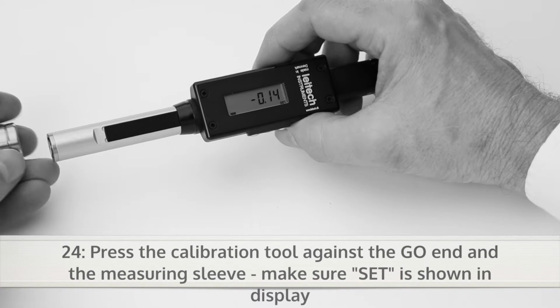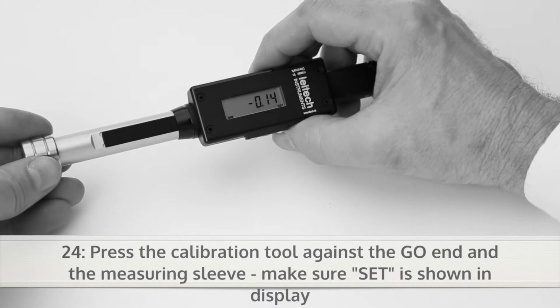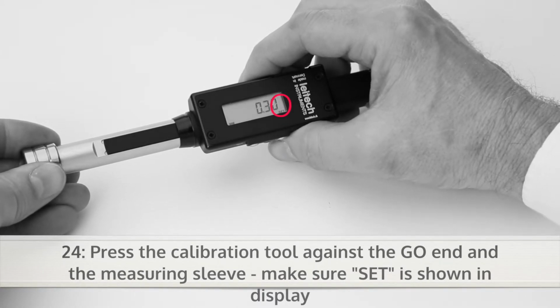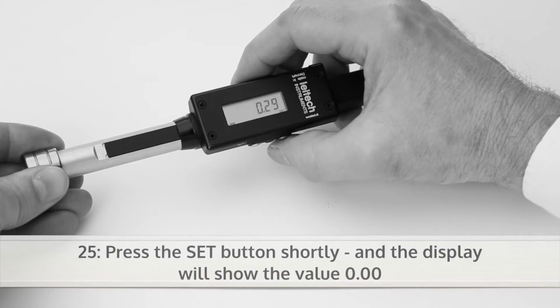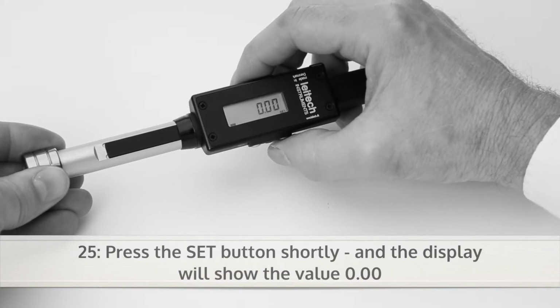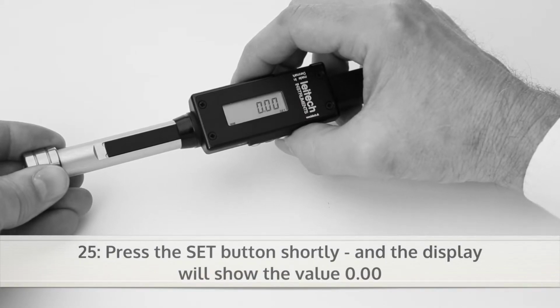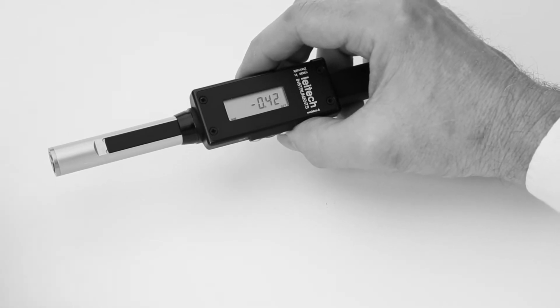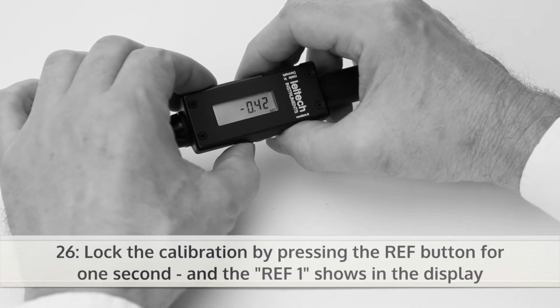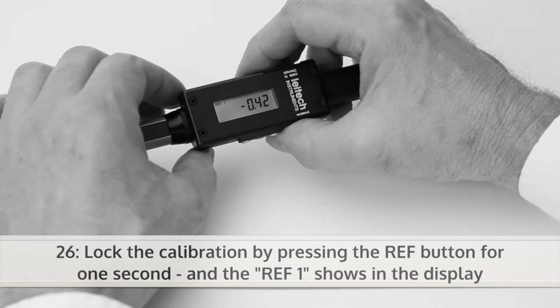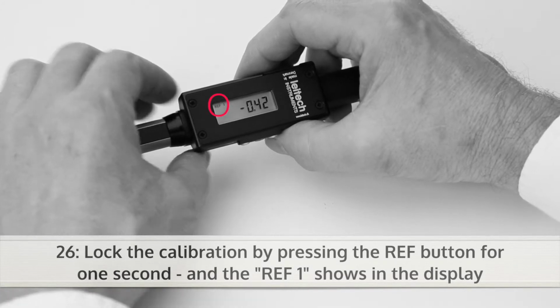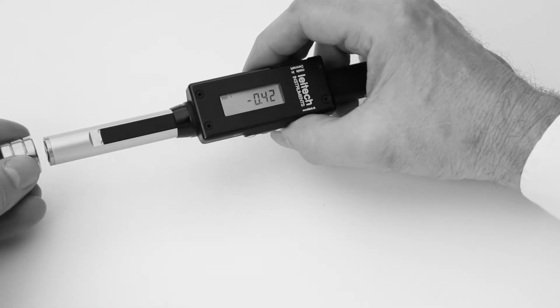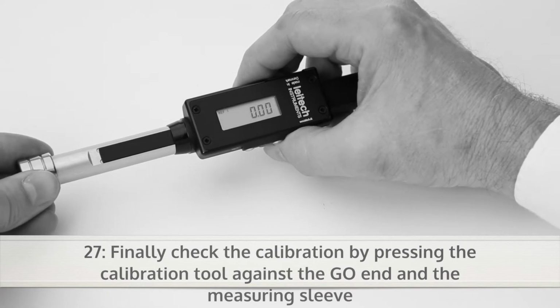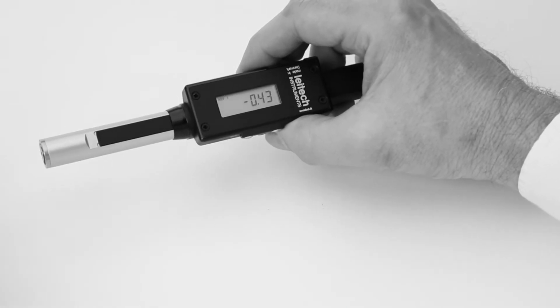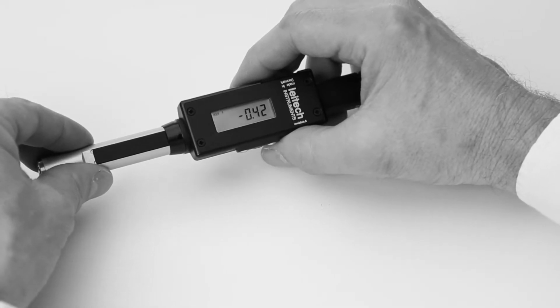Then press the calibration tool against the go end and the measuring sleeve, and make sure Set is shown in the display. Press the Set button shortly, and the display will show the value 0.00. Now save the calibration by pressing the Ref button for 1 second, and the Ref 1 shows in the display. Finally, check the calibration by pressing the calibration tool against the go end and the measuring sleeve.